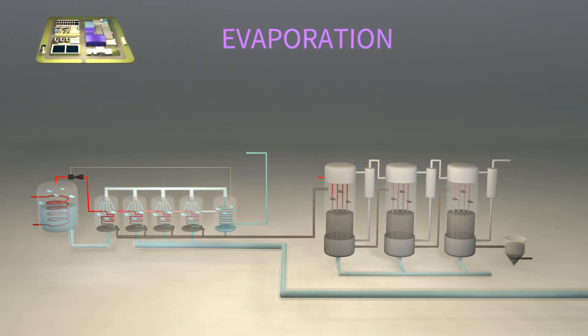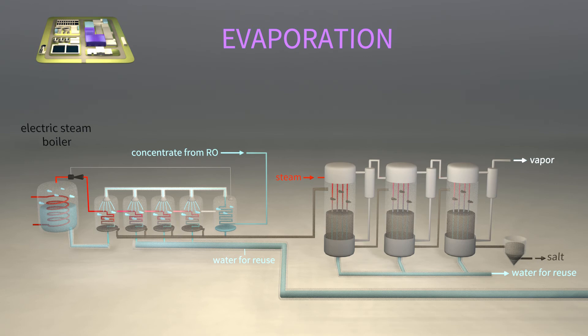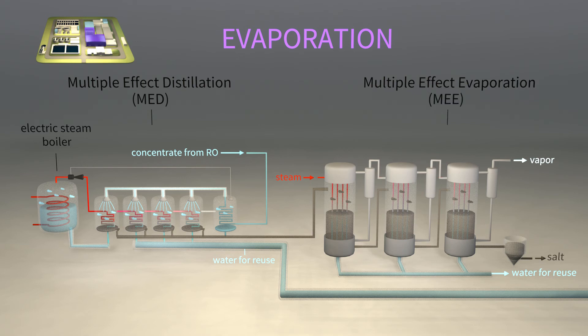In the evaporation, the concentrate is further concentrated by evaporating water until solid salt crystallizes. Evaporation is very energy-intensive. To make it more efficient, evaporation powered by an electric steam boiler is done in a sequence of effects. The units are called multi-effect distillation, MED, and multi-effect evaporation, MEE. The product is solid salt that can be used, for example, in the leather industry.